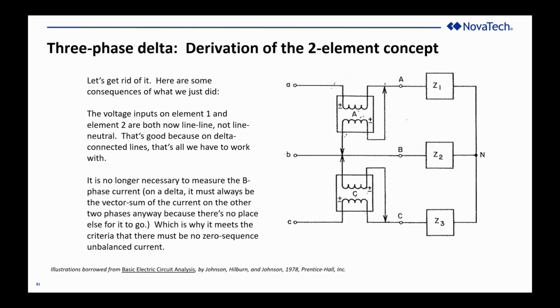We'll call them element 1 and element 2. In this case, because we've moved the common point to the B-phase conductor, the reference for both the element 1 and the element 2 voltage coils is the B-phase conductor. So I'm no longer looking at A to neutral, I'm looking at A to B. And on my second element, I'm no longer looking at C to neutral, I'm looking at C to B.